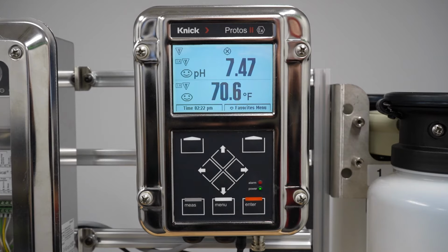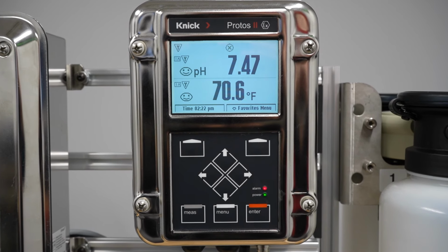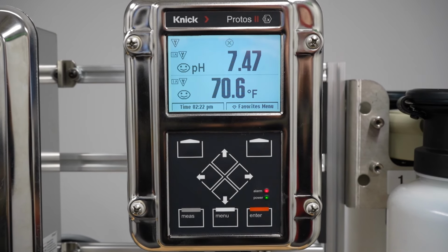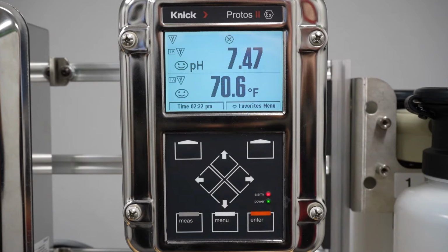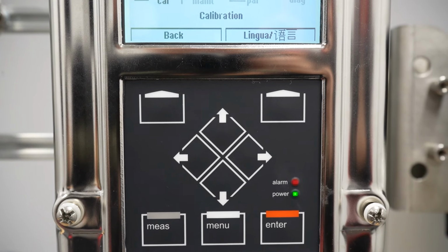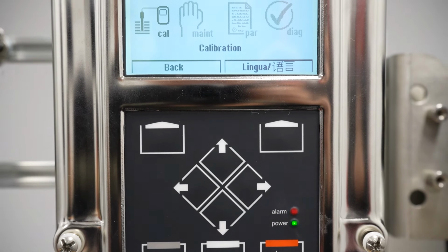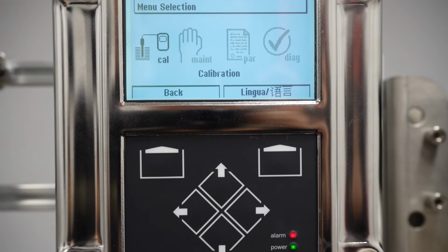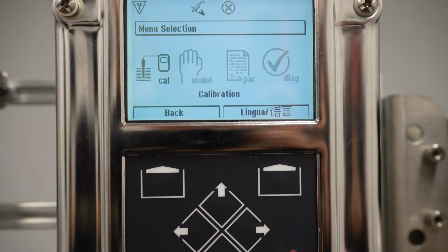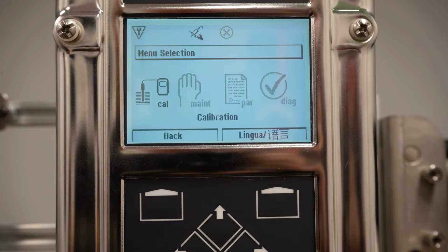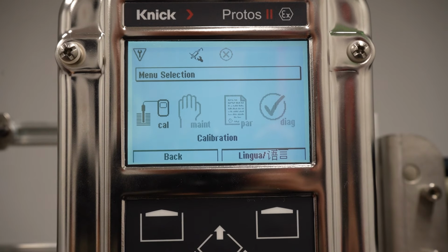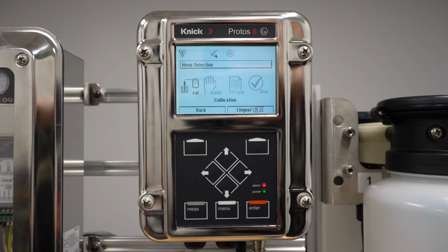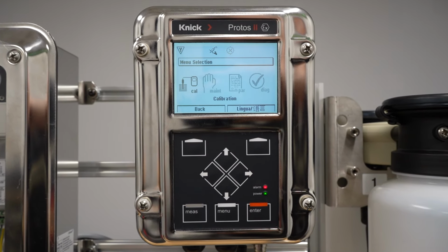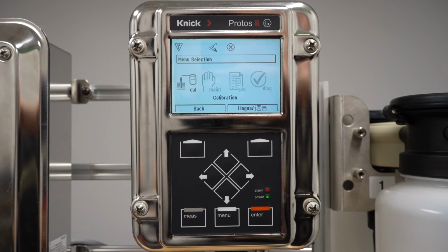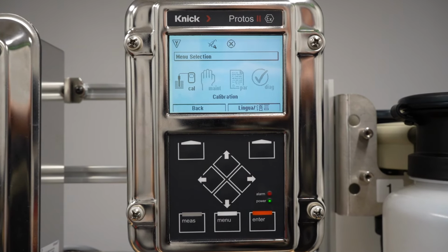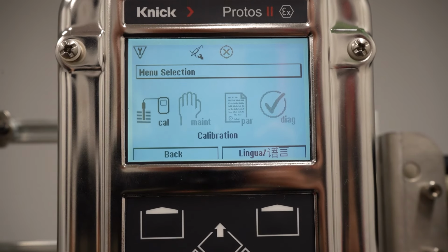The Protos transmitter provides the instructions to the Unical controller to activate the different programs, again based on the maintenance needed. There are programs for calibration, cleaning, and storage, as well as customizable programs for any special requirements the customer might have for their specific process needs. The Protos can also transmit the system and sensor diagnostics information, providing a constant status on the health of the entire system. This leads to the maximum accuracy.